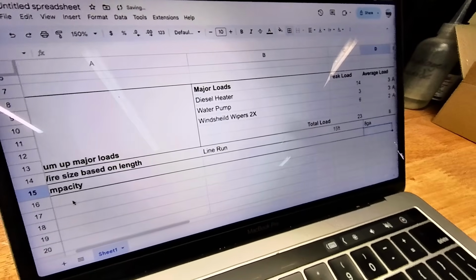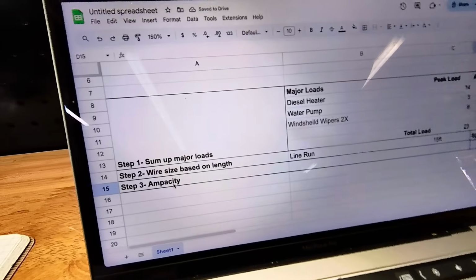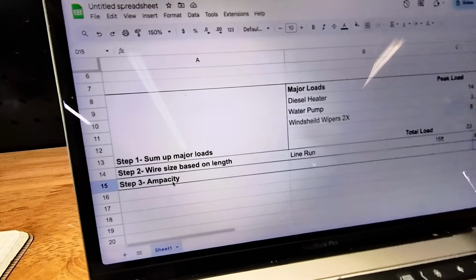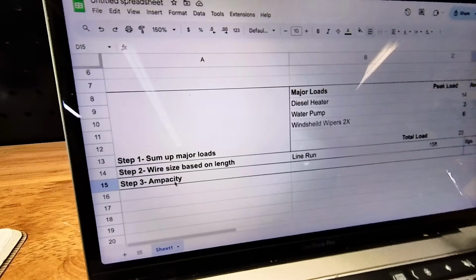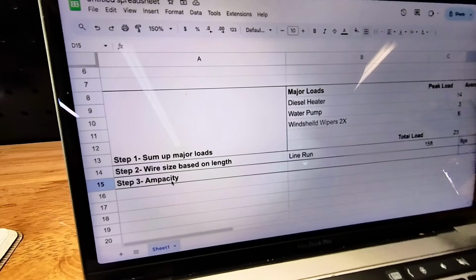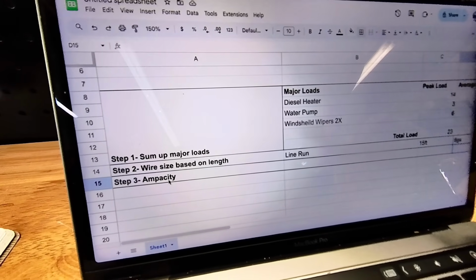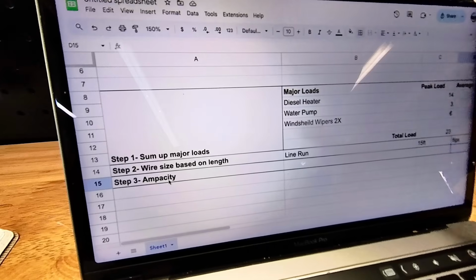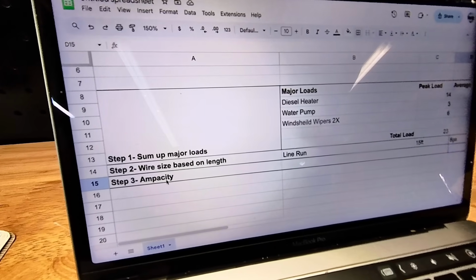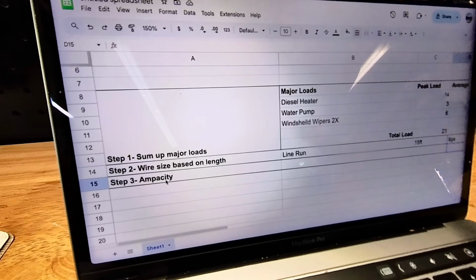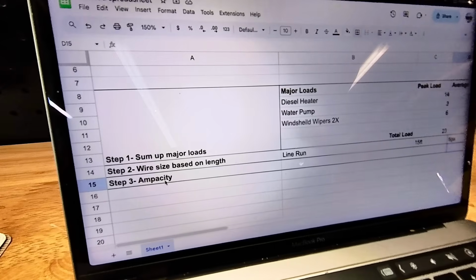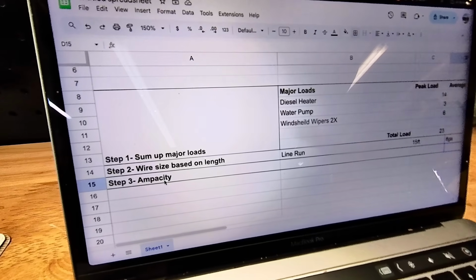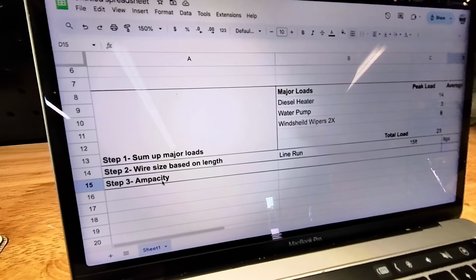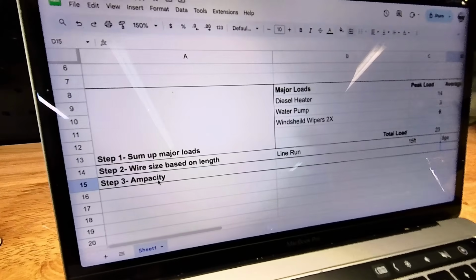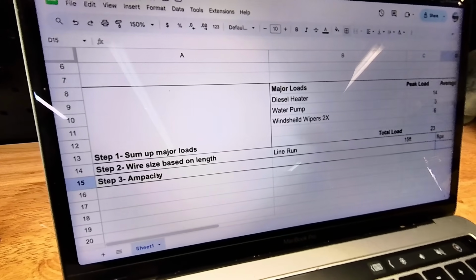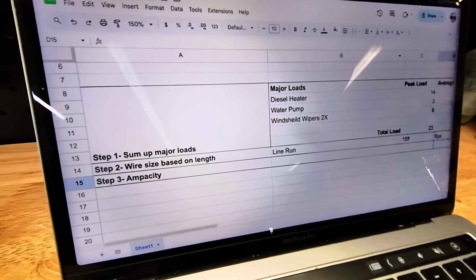Now the final step, step number 3, is determining the ampacity of the wire. That's a funky word, but it really means how much current in amps an 8 gauge wire can support. This depends on a few factors, like whether it's copper wire, how many strands are bundled together, and there's even a spec for whether the wire is in an engine room or not—I don't know if there's some kind of electromagnetic interference that plays into that equation you experience in an engine room and not elsewhere.